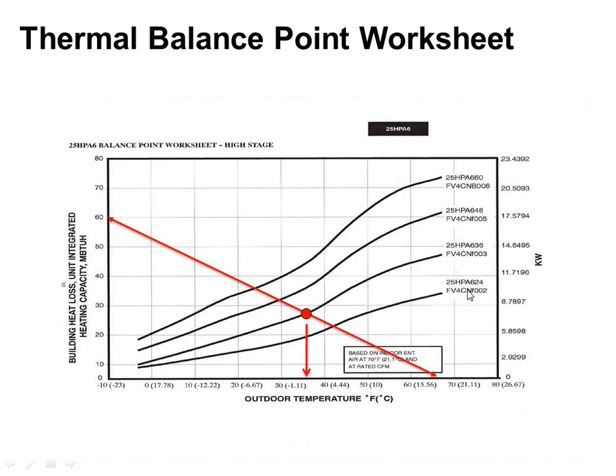There are 4 of them listed here, a 2, a 3, a 4, and a 5 ton, and then the half size would just be halfway in between, basically. So if I put a 2 ton heat pump in this guy's house, if I followed that line down, when I got to, we'll call it 43 degrees outside, I would no longer be able to make enough heat with the heat pump to heat this person's house. If I put the 3 ton in, which is where the red dot is, if I follow that line, at 36 degrees outside I wouldn't be able to make enough capacity below 36 degrees. If I put the 4 ton, then my cutoff point would have been whatever, 28 degrees. If I put the 5 ton in, I would have gotten down to 24 degrees outside.